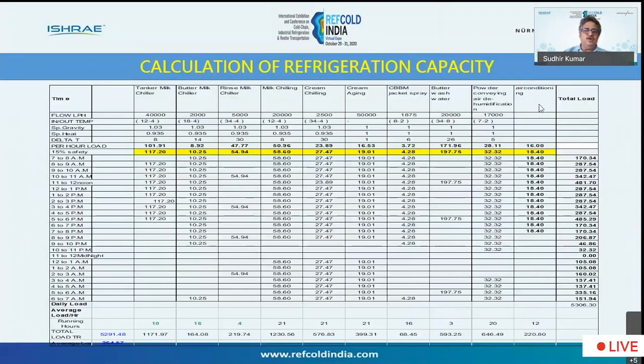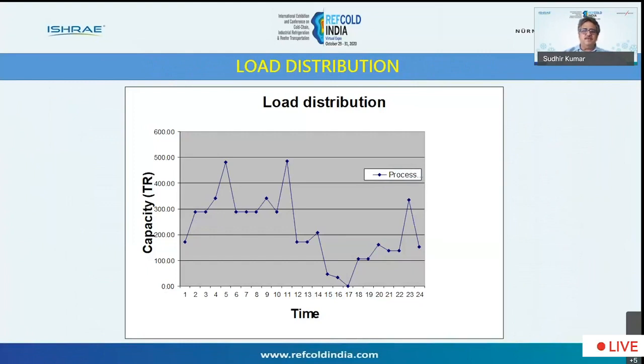So once you know the various processes, this is a very important part in designing a dairy plant. You need to know at what timing the milk is coming and what process you are doing, because if you start doing all the processes at a time, then your peak refrigeration load becomes very high. So it is better to stagger the loads, and based on the staggering of load, you design your refrigeration plant. Once you know the total heat load, once you plot it, then you can work out the peak load, base load, etc. If you see this chart, it will explain how it is.